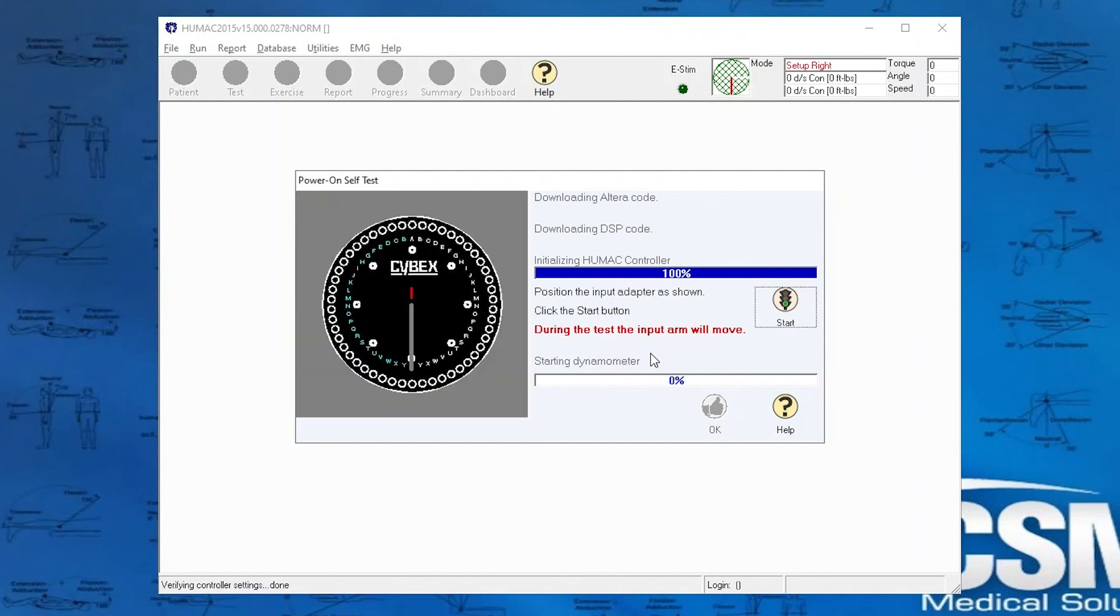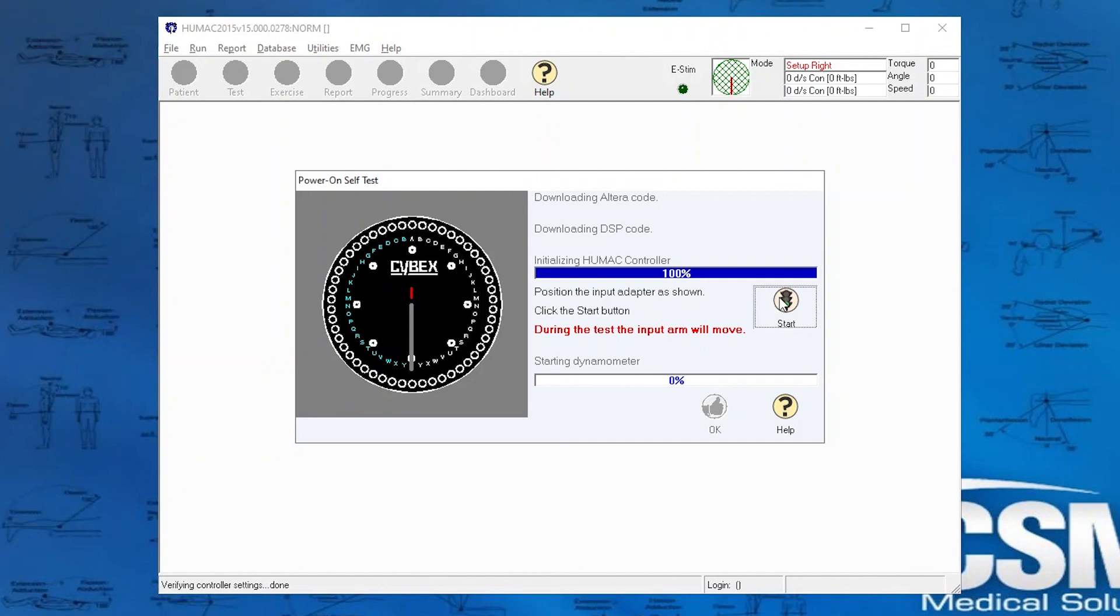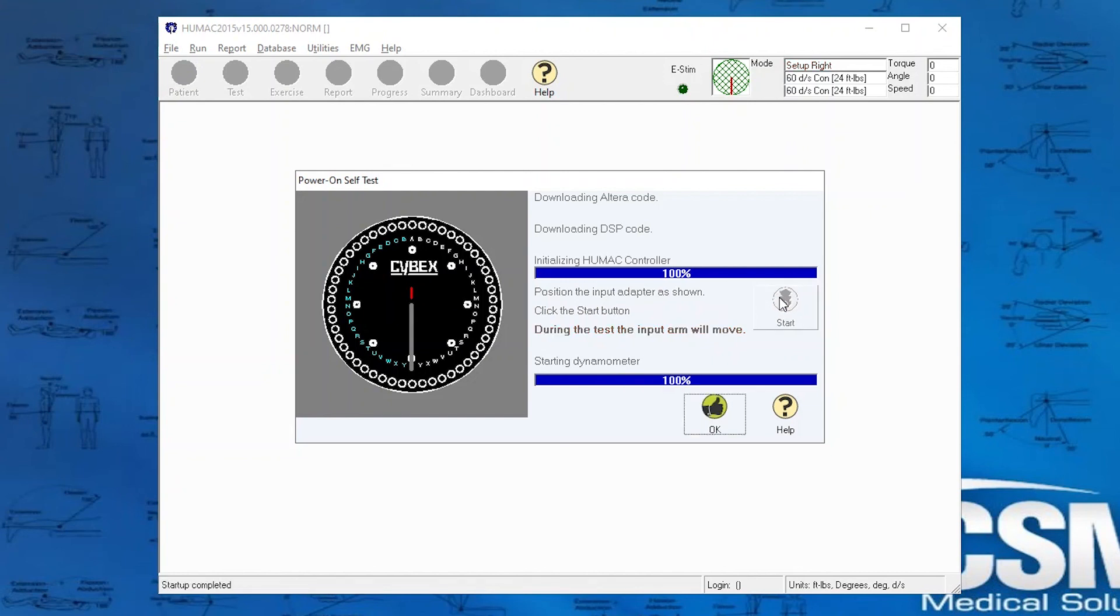What's also important on the Power On Self Test is that the input arm is at the 6 o'clock position as it's shown on the screen. The red tick is above the little gap. So we set our input arm perpendicular at 6 o'clock, and then we press Start.